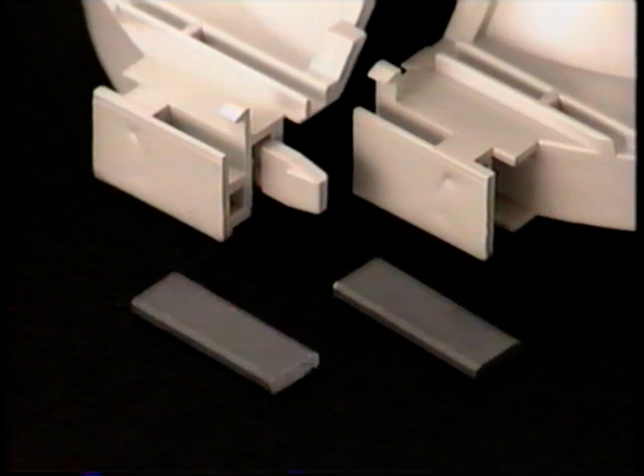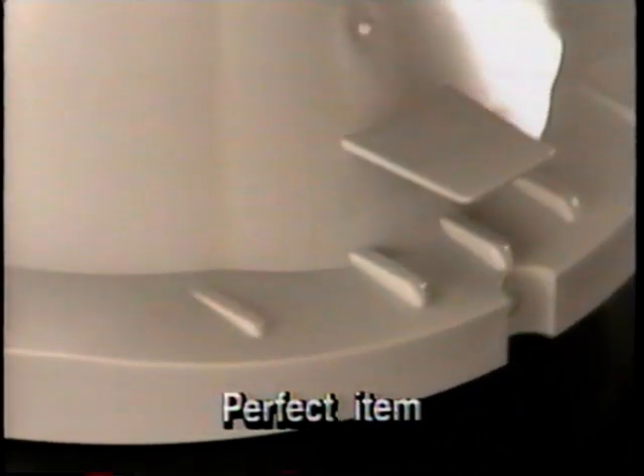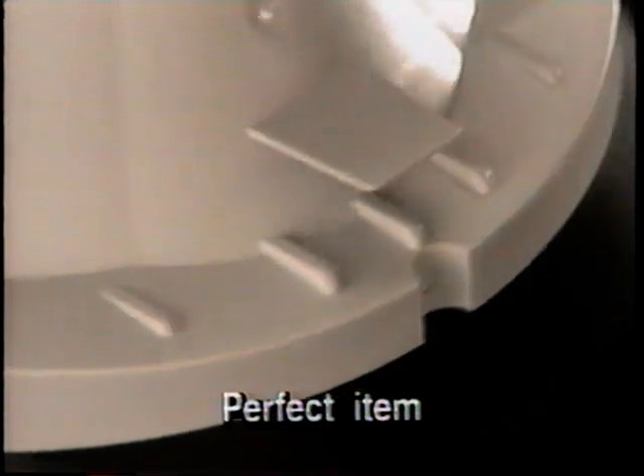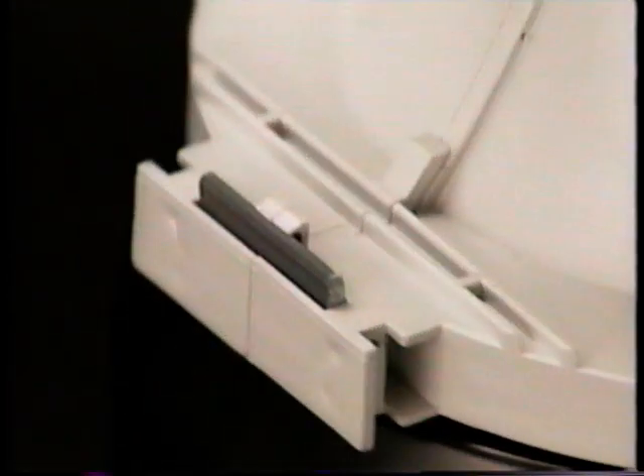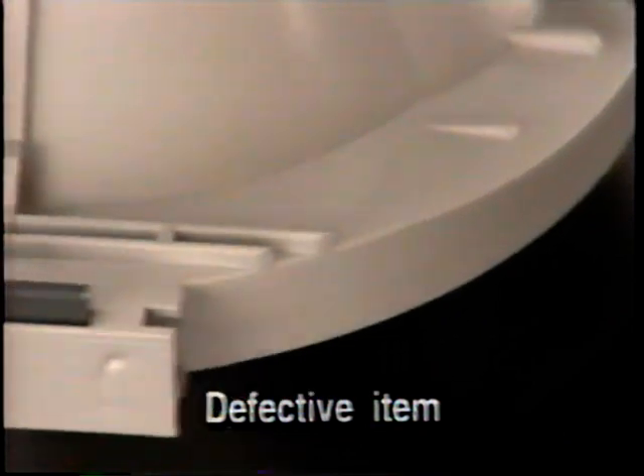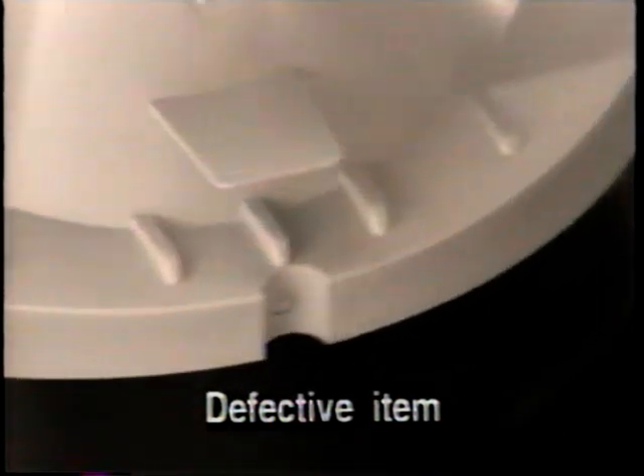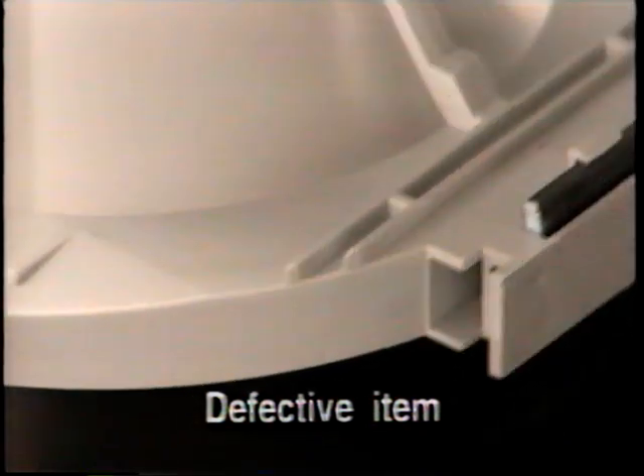Magnets have to be installed in the right and left ditches of the separator to correctly meet the electrodes. The north and south poles are color-coded. However, before improvement, operators sometimes mounted one of the magnets in reverse or even missed installing one of them altogether. These mistakes were not discovered until the adjustment process. This is how the magnet should be mounted.